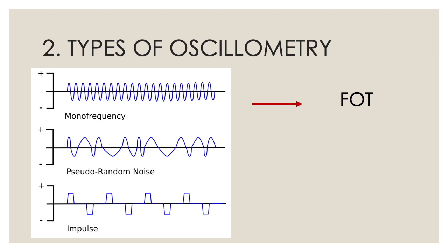So at a time, we may give 5 Hz, then the generator will produce 7 Hz, 20 Hz, 30 Hz, varying depending on whom we are testing. Whether we are testing children, where we may have to measure from 7 Hz till 30, or we are measuring adults where 5 to 20 is sufficient. So these are called forced oscillation techniques.